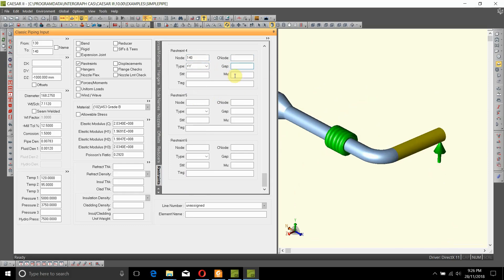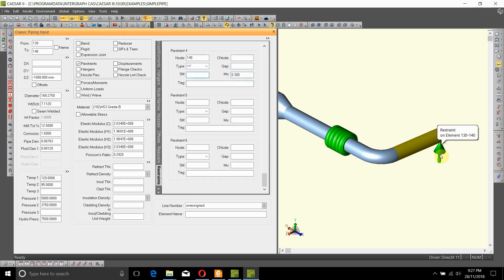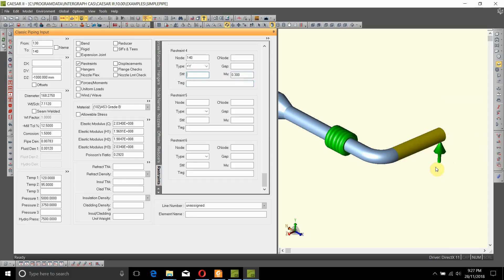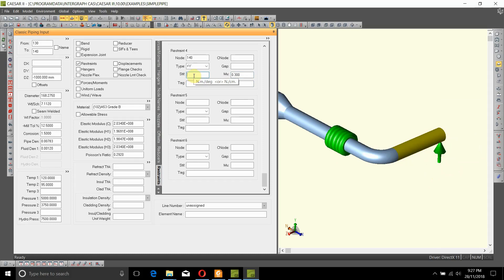If this pipe is resting on steel, you can add a friction coefficient in here. For steel to steel, 0.3 is the friction coefficient. If it is supported on a T post, channel section, beam, or column where it is not 100% stiff but is a bit flexible, you can add the stiffness of that member in here.